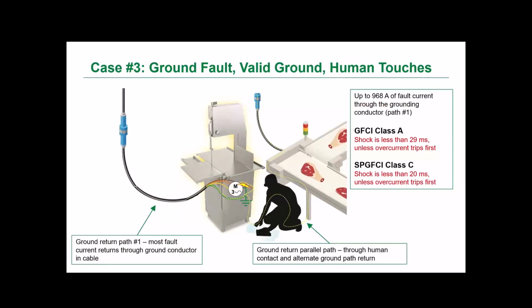So looking at case number 3, we're considering the case of a normal, healthy ground conductor in the cable and a ground fault in the equipment. And now, again, the same cases of a human making contact with that equipment. Now here, both the Class A GFCI and the Class C special purpose GFCI would initially allow this equipment to be started. And based on the calculations with the cable type that we had shown on that slide earlier, the fault current could be up to about 1,000 amps, returning through the equipment grounding conductor.